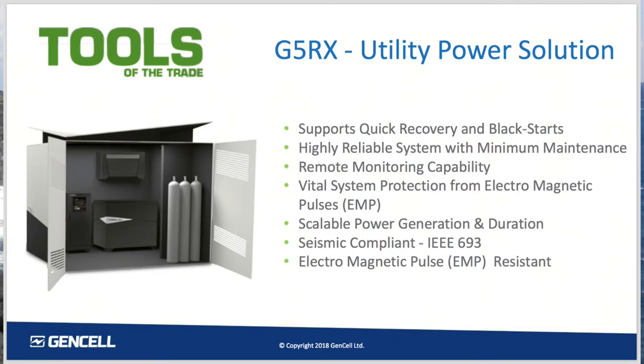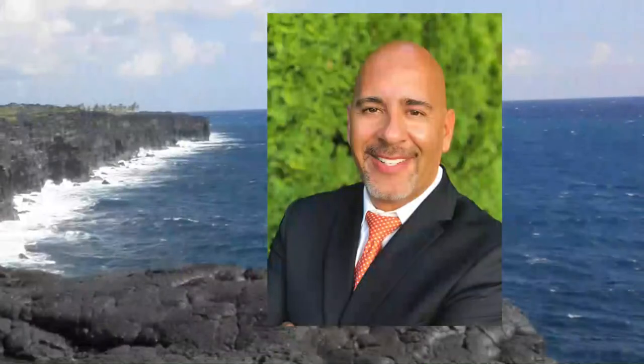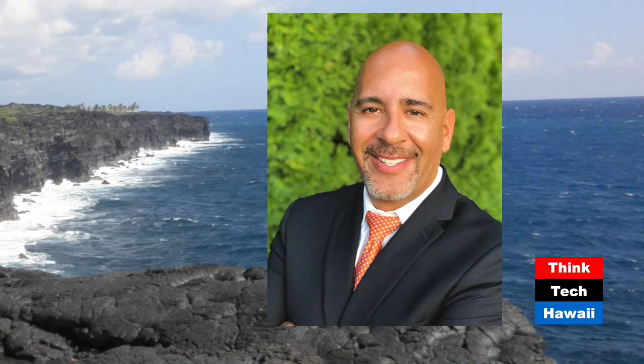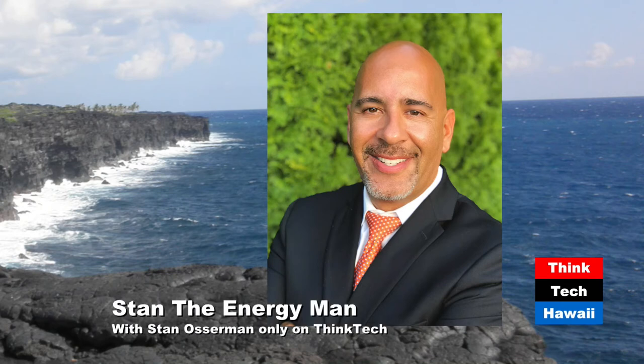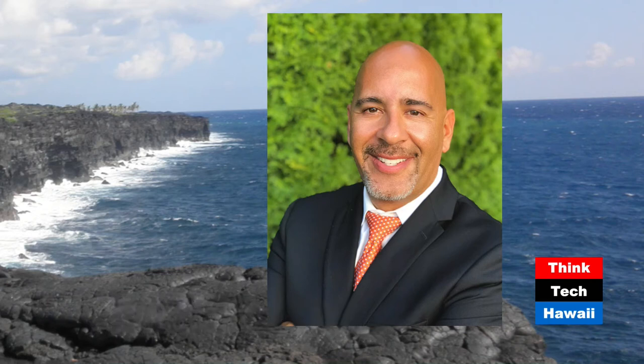After an 8-hour period, the problem is that basically the whole system shuts down and the utility is not able to remotely turn these systems back on. The biggest challenge is that a lot of these substations are typically in very remote locations, so it could take anywhere from a couple of hours to 5, 6, 7 hours just to travel to these substations and bring a generator, more batteries, or whatever's needed. It becomes a big problem, especially if multiple facilities are shutting down simultaneously.